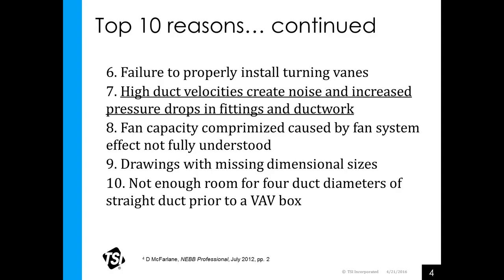Not understanding the fan system effect can also compromise fan capacity. And again, that goes right back to the system design, right on up through the operation phase. A lot of times, drawings don't have the proper dimensional sizes. And in commercial applications, it is very important to make sure that you're faithful to and following the schedule and the installation drawings, even when going back and doing routine maintenance.